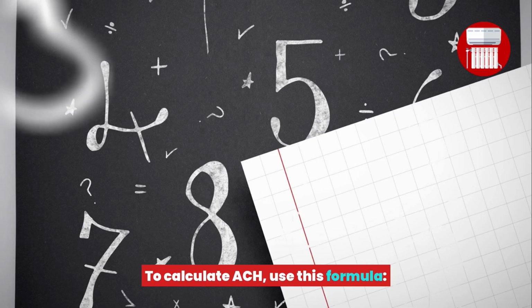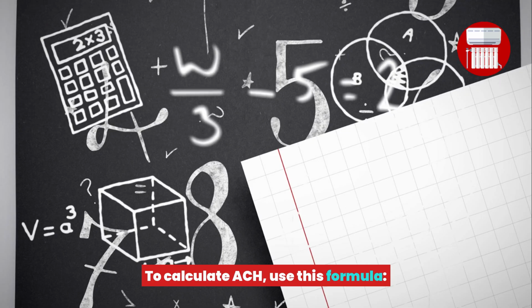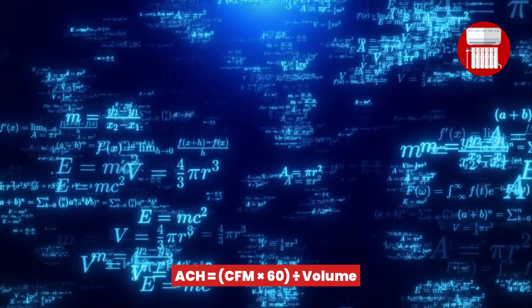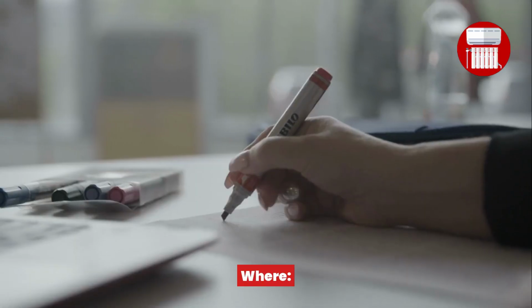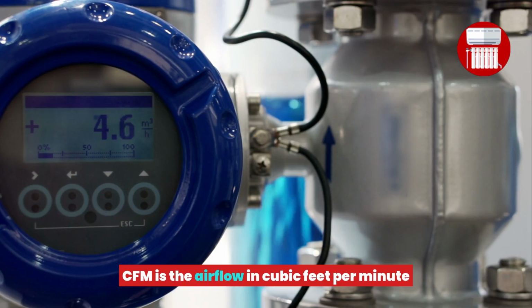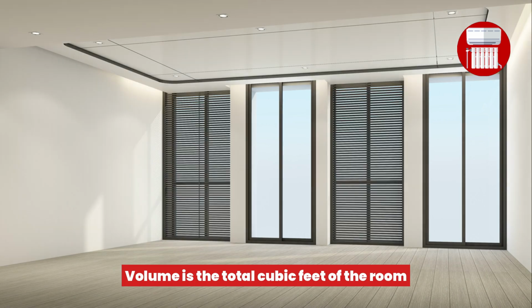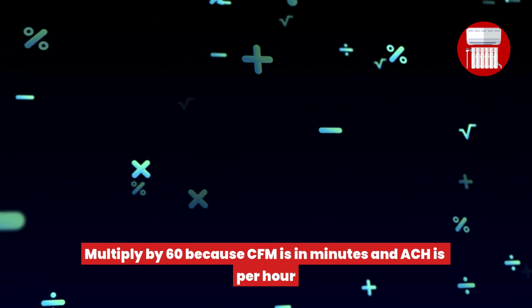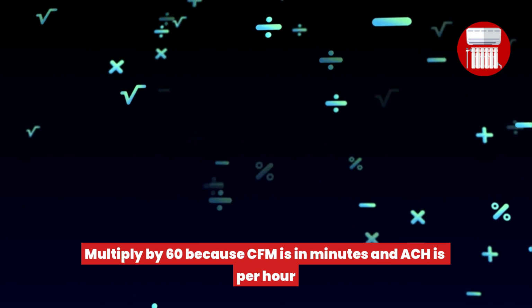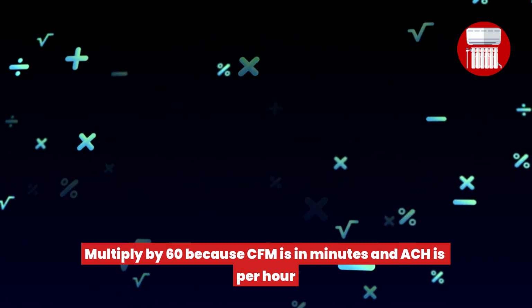The formula. To calculate ACH, use this formula: ACH equals CFM x 60 divided by volume, where CFM is the airflow in cubic feet per minute, and volume is the total cubic feet of the room. Multiply by 60 because CFM is in minutes and ACH is per hour.